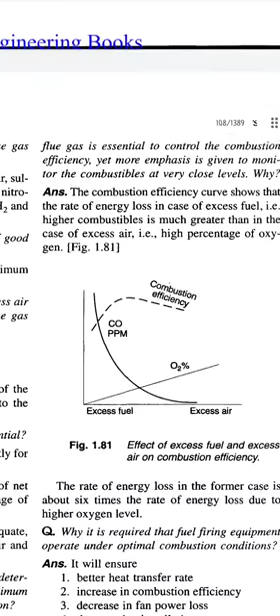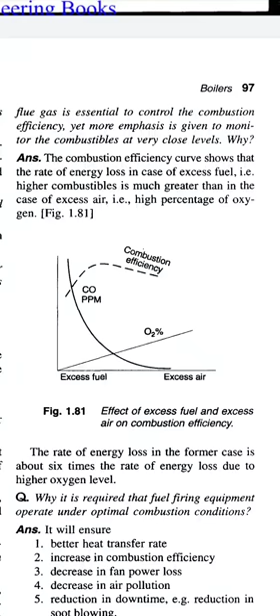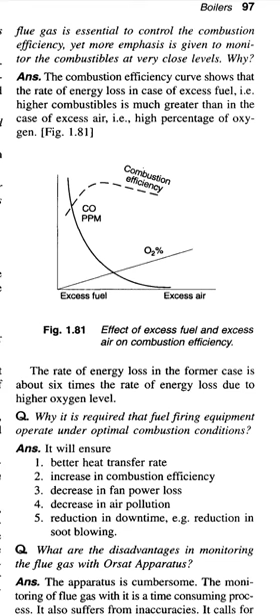Why? The combustion efficiency curve shows that the rate of energy loss in case of excess fuel, meaning higher combustibles, is much greater than the case of excess air, meaning high percentage of oxygen. The rate of loss in the former case is about 6 times the rate of energy loss due to higher oxygen level.